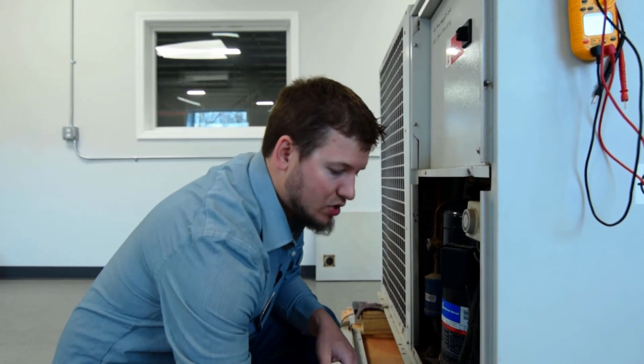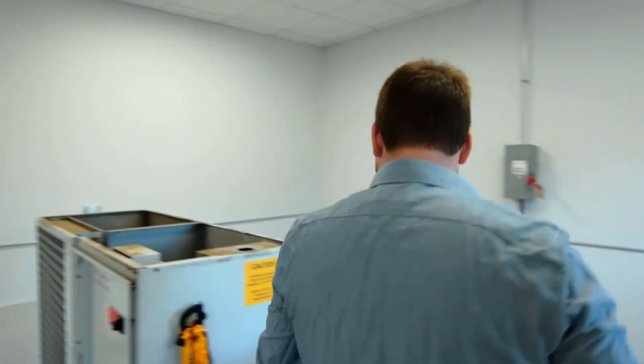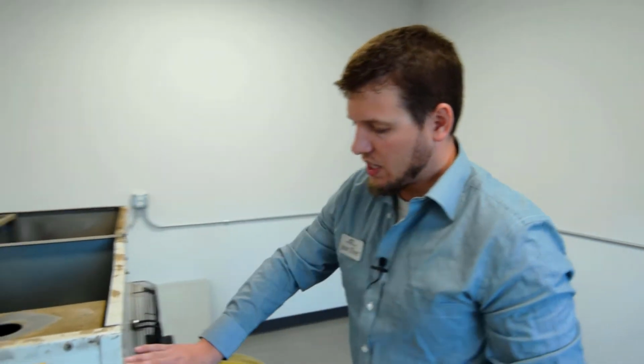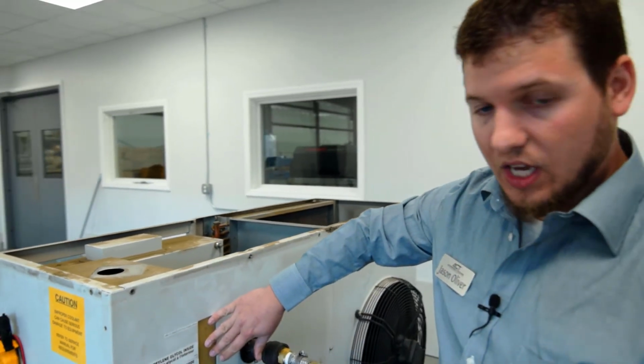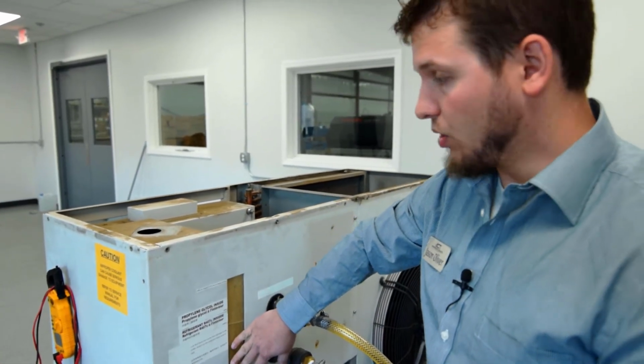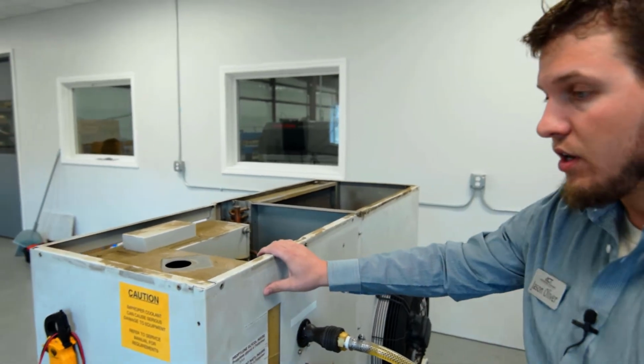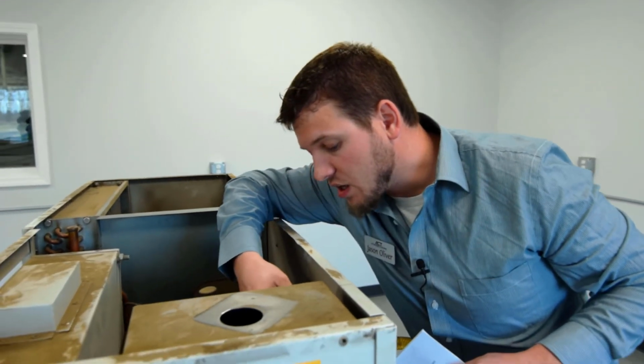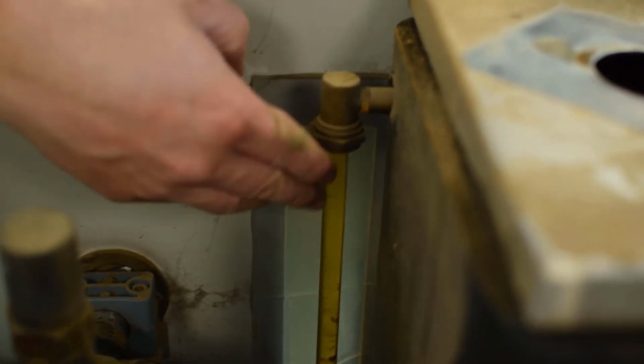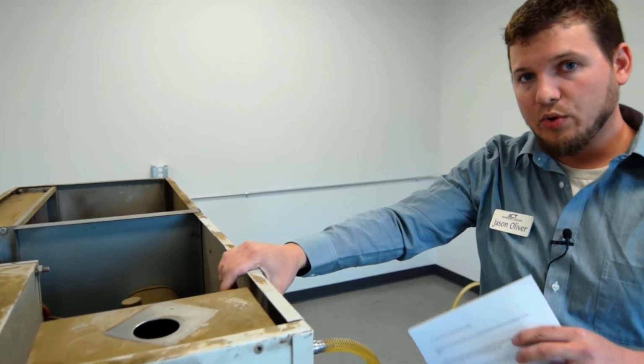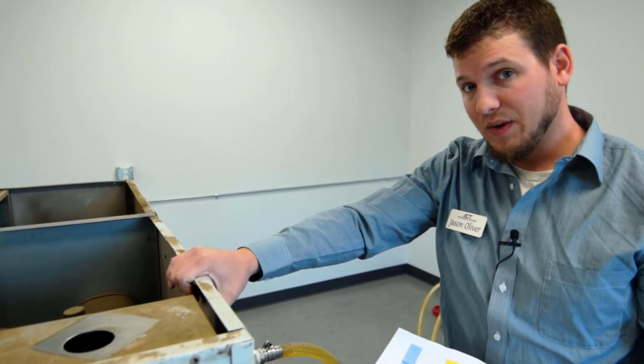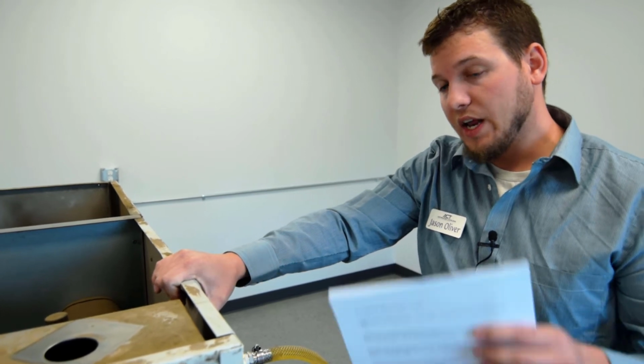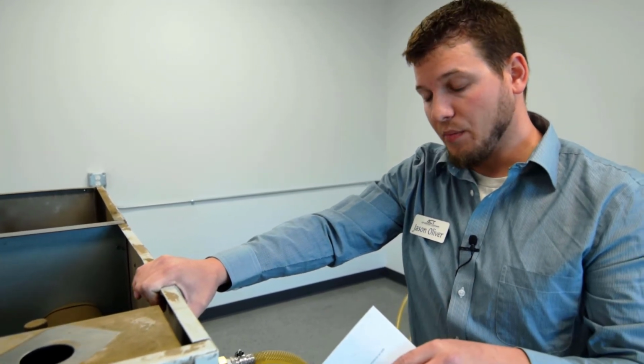Once you've figured out what the concentration of the glycol in the system is, step number 4 is to verify that your tank is completely full. On this chiller, if you come over here and take a look, you're going to notice that the sight glass, or the viewing window to see the sight glass, is cloudy, so you're unable to see through. Luckily, we removed the top cover, so if you look above here, you can actually see that this sight glass is currently full. If the sight glass was not completely full and you had a percentage of glycol that was less than 50%, this would be the time that you would add a higher concentration to get it to the 50% mark. Once you have that completed, we're going to go ahead and move on to step number 5 on this checklist.